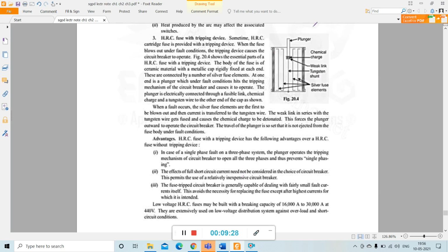So this is an HRC fuse with tripping device. Its construction is the same as the HRC cartridge fuse. This is the cartridge ceramic body, and this is the brass end cap, at both end sides. The body of the fuse is of ceramic material with a metallic cap rigidly fixed at each end. These are connected by a number of silver fuse elements. See, this is the number of fuse elements, and these are connected with the end caps, and at one end is a plunger.